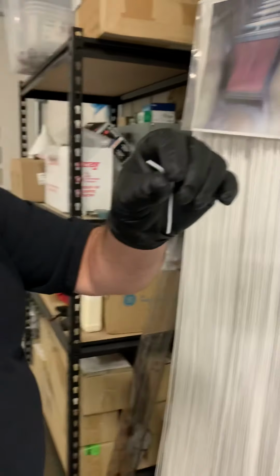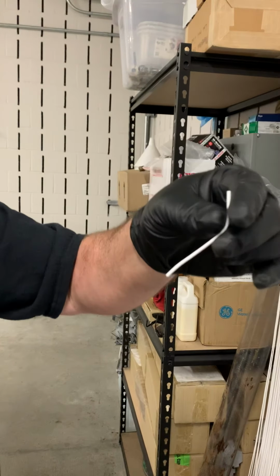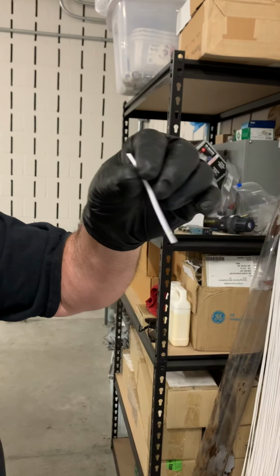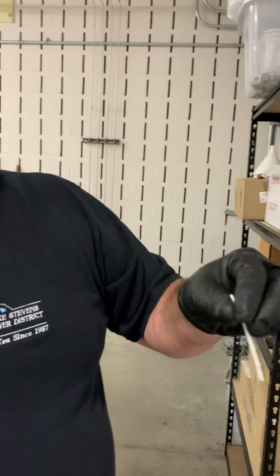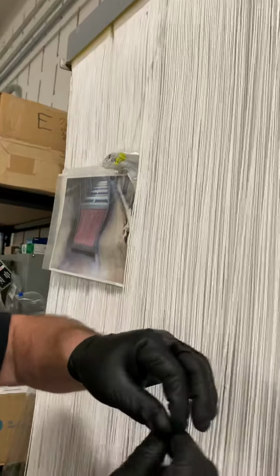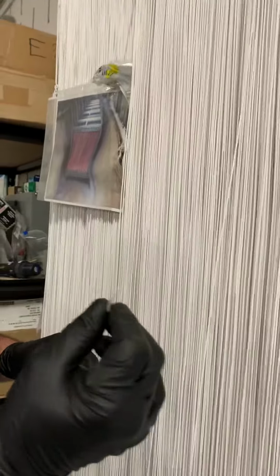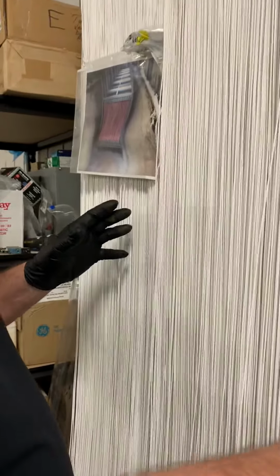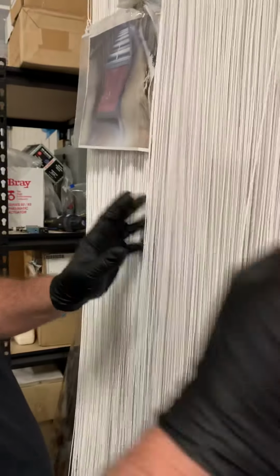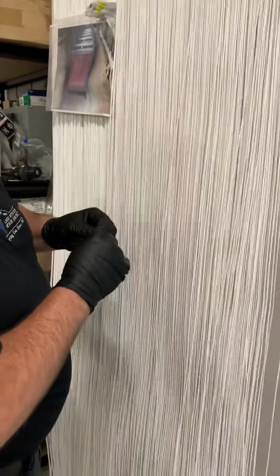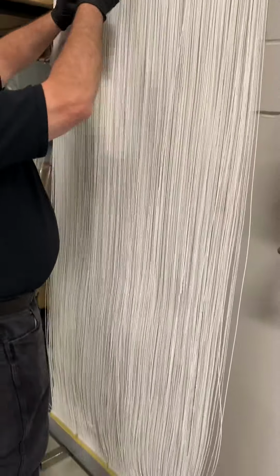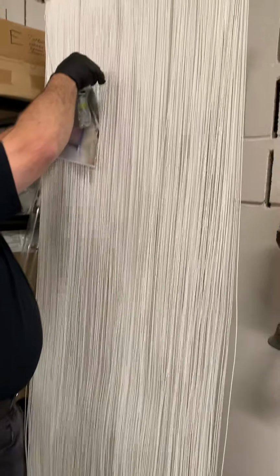These are the magic, these are the hollow fiber modules. They have a nominal pore size of 0.04 micron, which will hold back all known bacteria and most viruses when you filter it. So we apply a light draw to the inside of these membranes, just like you would suck on a straw, and it filters all of that nasty stuff. All of the biomass stays on the outside, and the clear water is drawn through the pores of the membrane and sent to the effluent room for our final effluent.